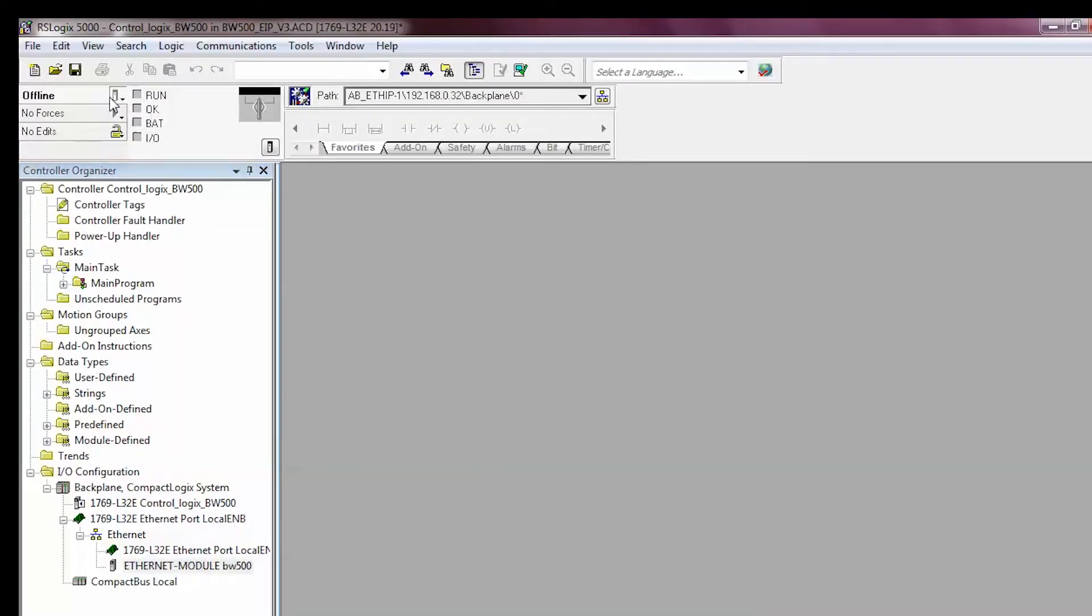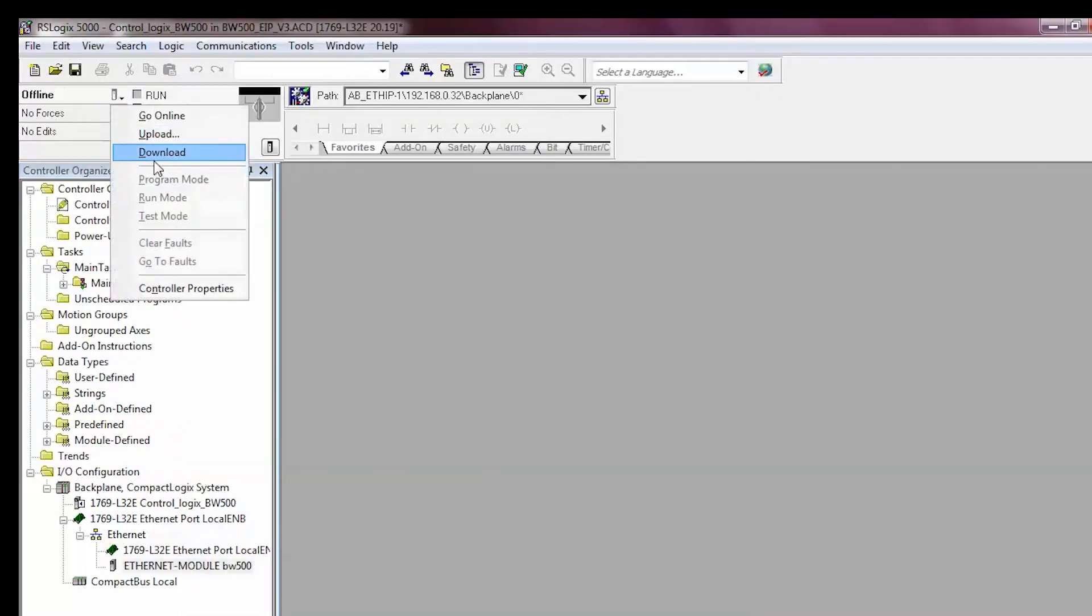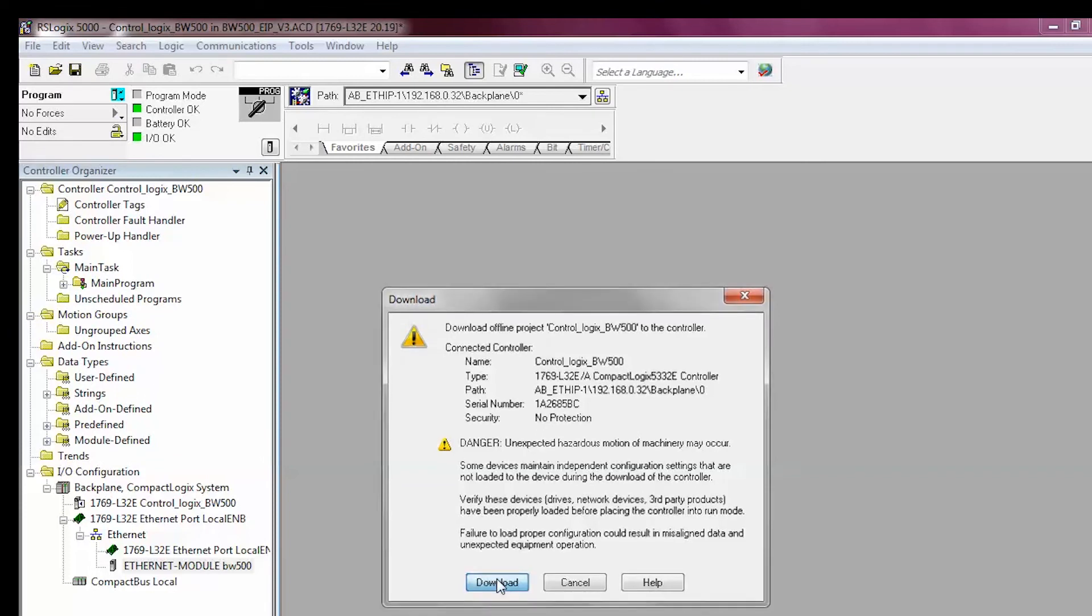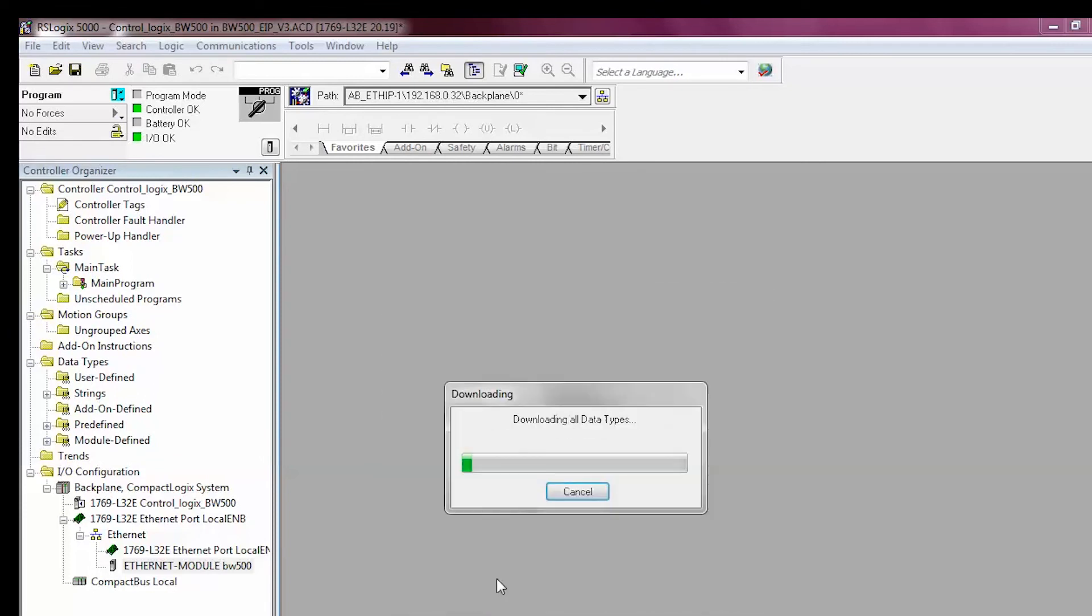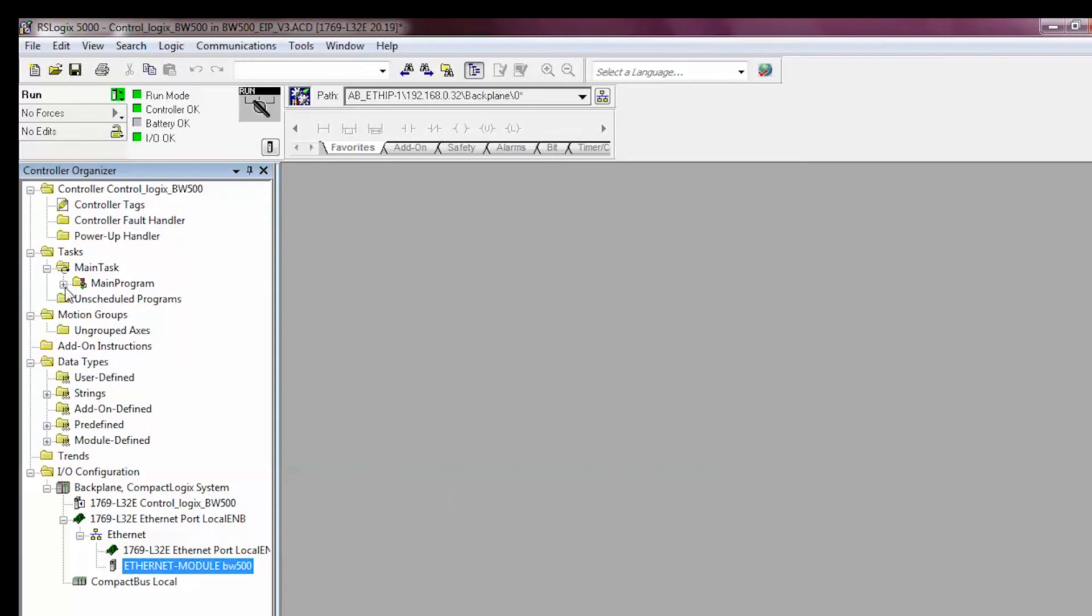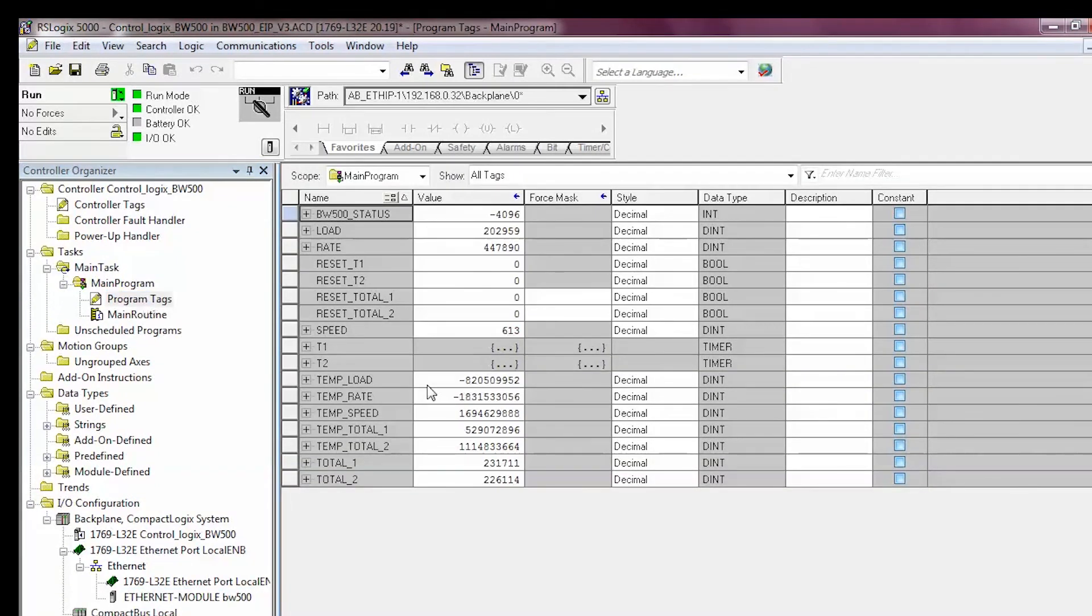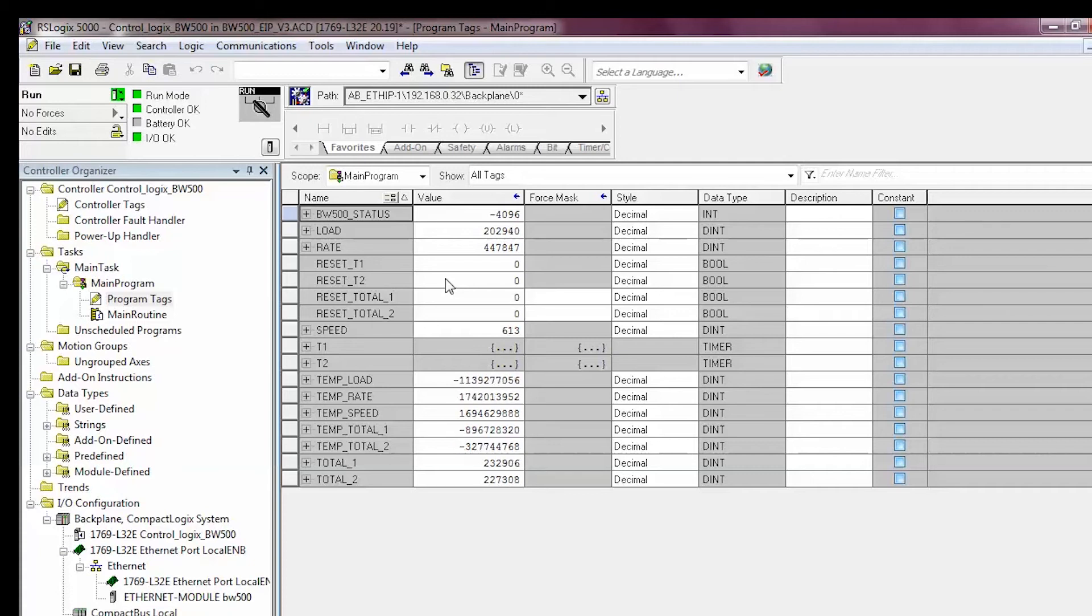Download the configuration to your PLC. With the PLC in run, navigate to the main program folder, Program Tags. View the process values coming back from the BW500. Compare the process values to the BW500 display to confirm that everything is working correctly.